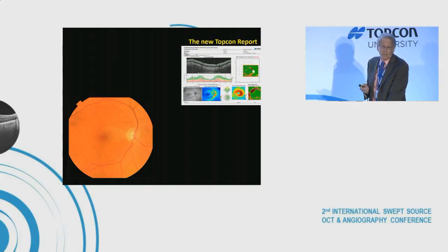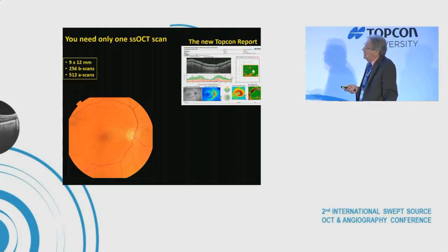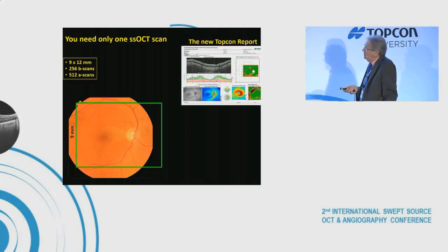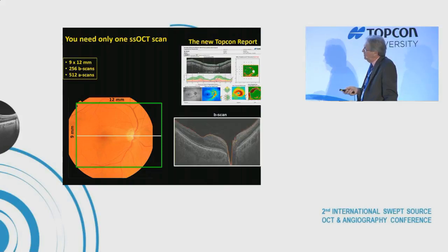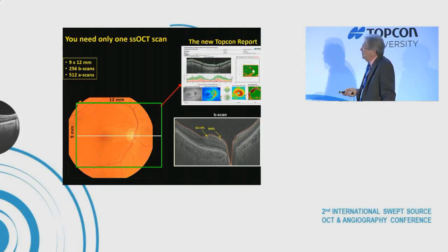Because swept source is so fast, we can now do all of that with a single scan. The scan we use is 9 by 12 millimeters — a wide field scan available on the Triton and Maestro. It has 256 B-scans, with the B-scan through the fovea showing the ganglion cell plus inner plexiform layer and retinal nerve fiber layer, with 512 A-scans per B-scan.